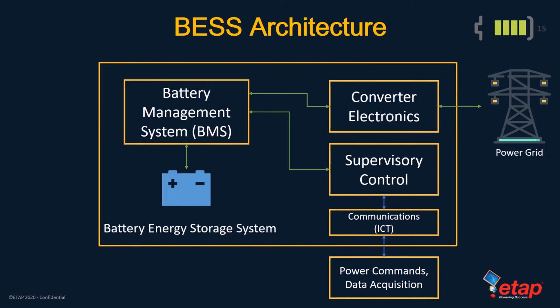So when we apply a lithium-ion battery in a battery energy storage system, this is a typical or traditional BESS architecture. It consists of the lithium-ion battery connected through a battery management system or BMS that is able to transfer power to the power grid through converter electronics. The converter electronics is essentially bidirectional, allowing the battery to charge and discharge through the BMS using supervisory control. The supervisory control can be communicated through ICT infrastructure to a microgrid controller or to a SCADA system, or the BMS may have its own local supervisory control that makes decisions on when to charge and discharge the battery based on the state of the power grid.